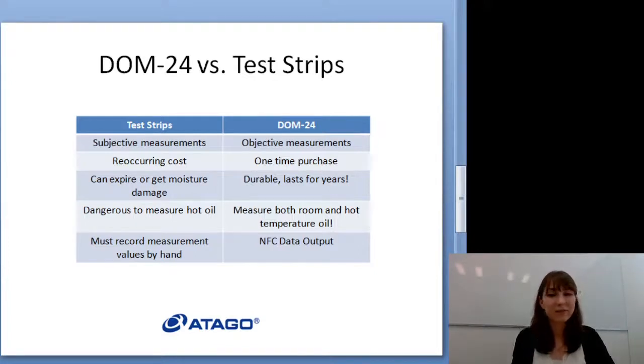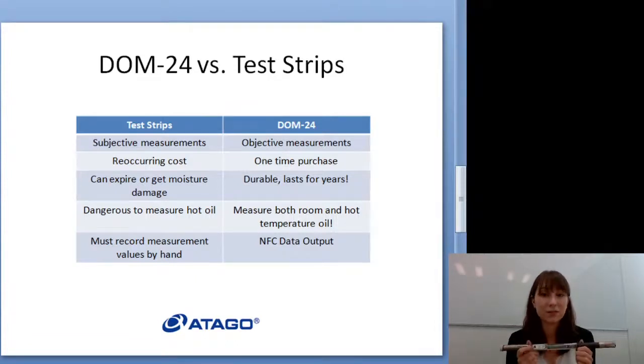Yeah, so DOM-24 doesn't really need to be calibrated often. Maybe after you've had it for a while and you want to check the calibration yourself, there is a calibration standard that you can buy from us. We don't have it come with the instrument because you really don't need to do it very often. The instruction manual goes over very well how to calibrate with the oil. But if you do need it, it's probably good to contact us first for troubleshooting so we can help you decide if you really need to calibrate it or not, or if there's a different setting that maybe you entered, or something else going on. So there is calibration solution, but I recommend to contact us first before just getting it.